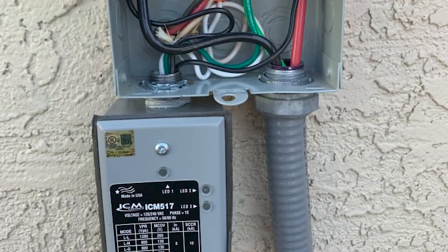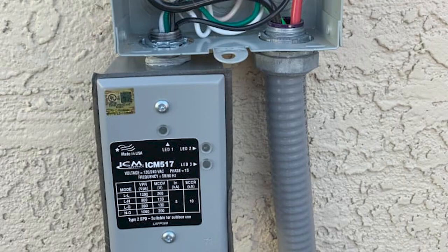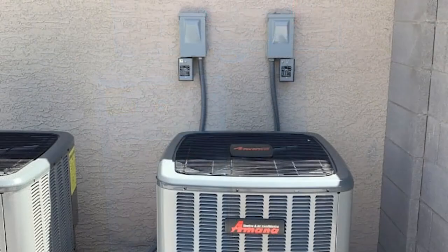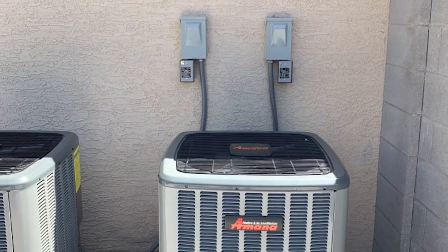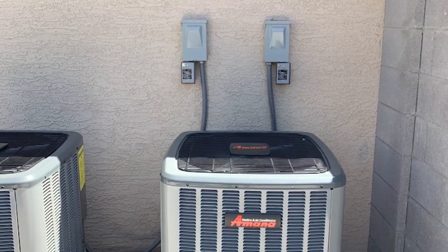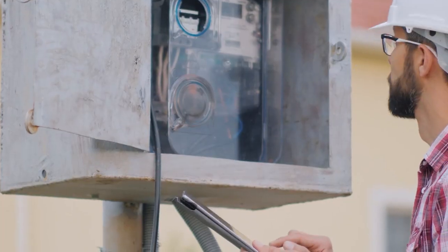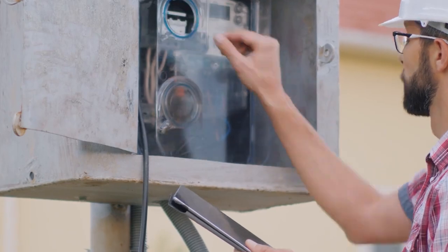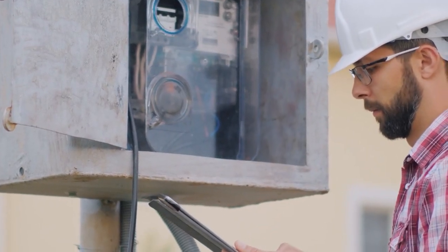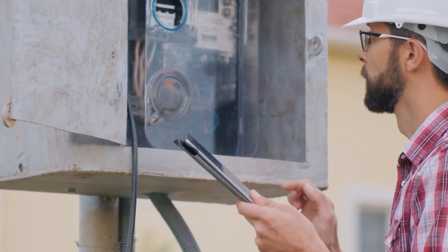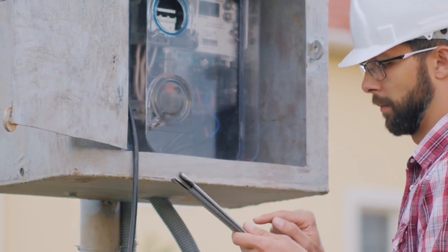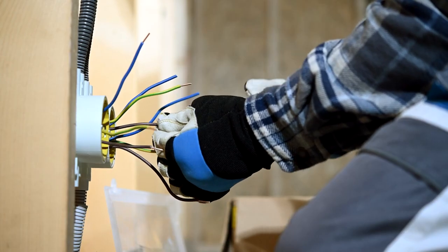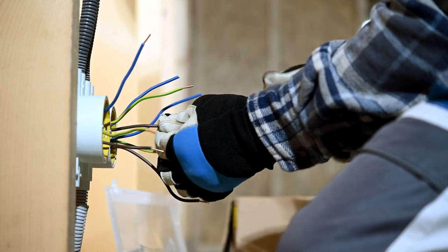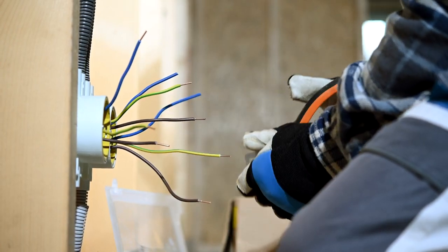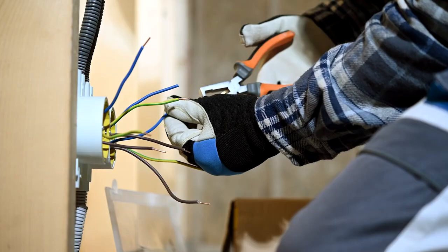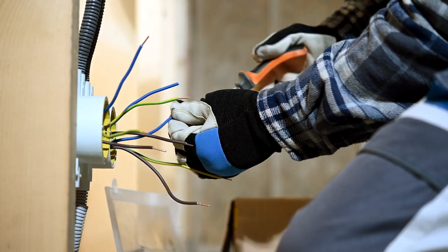Due to code, Type 1 devices have to be installed by a licensed electrician, thereby adding to the install times and costs associated with both installing and servicing the device. With a Type 1 whole house surge device, the homeowner would have to wait for a licensed electrician to come out to their home and shut down the power to the home each time they had to service a unit. The ICM 517 can be quickly installed by the HVAC contractor at the time they install the unit it's intended to protect, and easily service the device when needed.